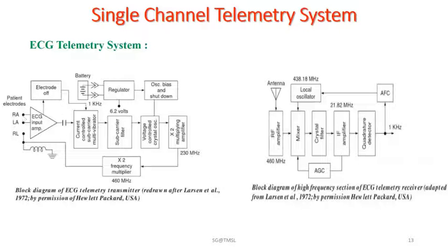Then the input circuit must be protected against large amplitudes due to the defibrillation technique, and this input amplifier must be AC coupled to the subsequent stages. Coupling capacitors are needed to eliminate the DC voltage and determine the low frequency cutoff of the system, which is usually in the 0.4 hertz range.